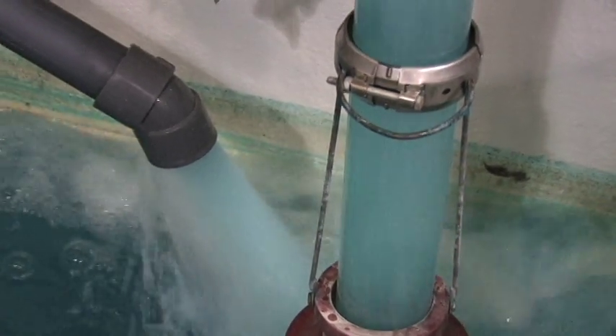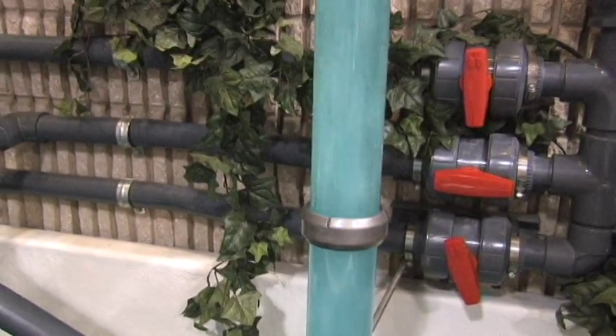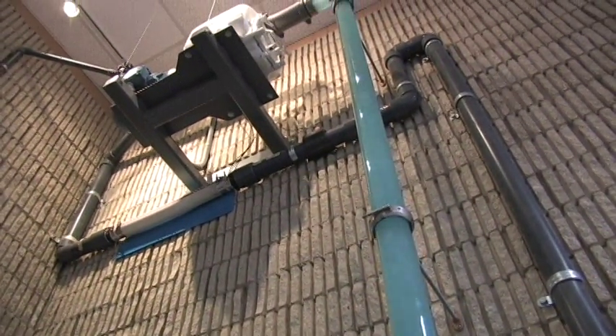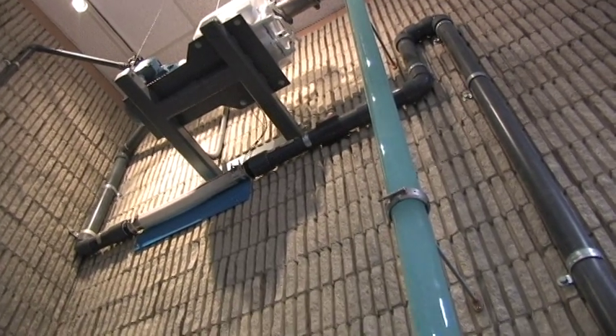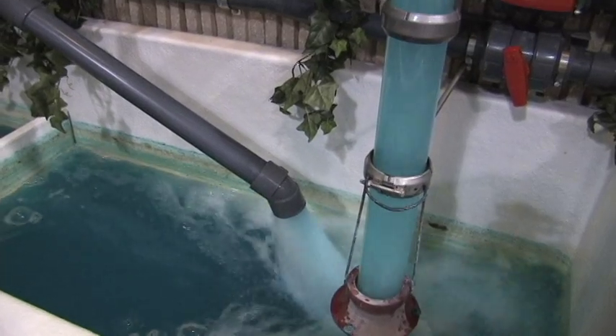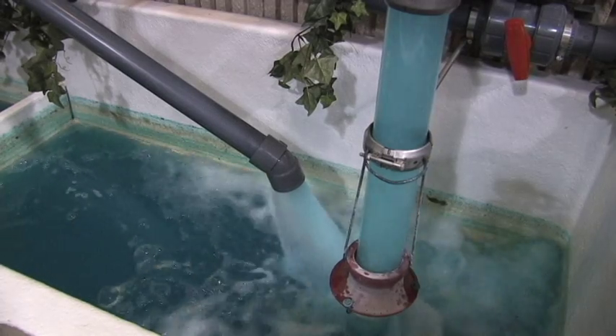There's a hydraulic imbalance inside of the pump now that over time could cause some bearing issues, but more importantly it could cause the pump to lose its prime. Now this is a self-priming pump by Gorman-Rupp — it's designed to handle a certain amount of air, so it can take care of a lot of air and keep itself pumping, but you can occasionally hear it coming in and out of a partial prime situation. If this were a submersible pump, when the air would get underneath the submersible it could cause that submersible pump to be air bound almost immediately and stop the flow coming out of the pump station, and that pump would trip out on a high temperature.